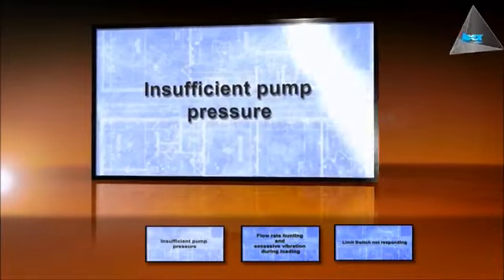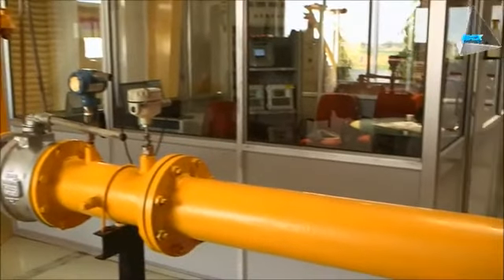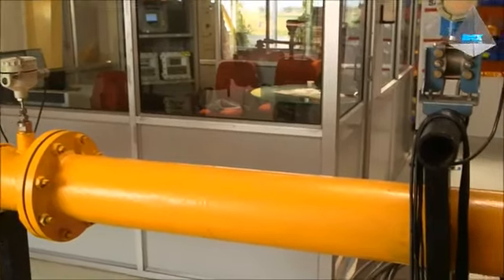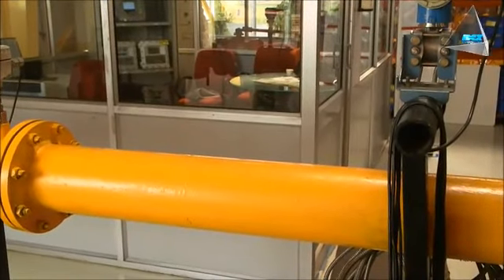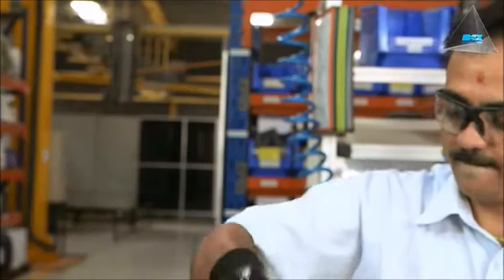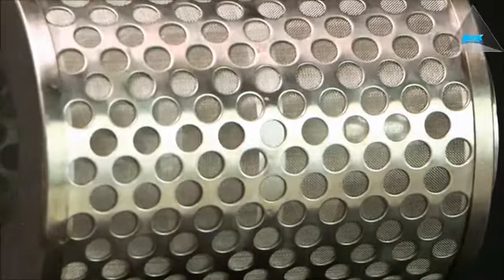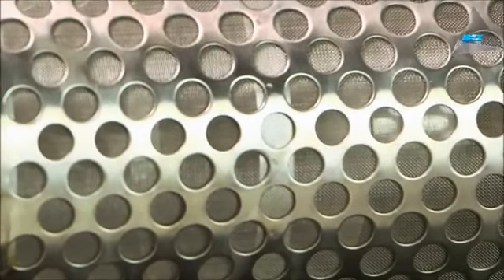Insufficient pump pressure. Solution: check the pump pressure and any partially closed valves in the header line. Ensure that the header valves are open. Check the metering system strainer basket for any clogging. Clean the basket if the metering system strainer is clogged.